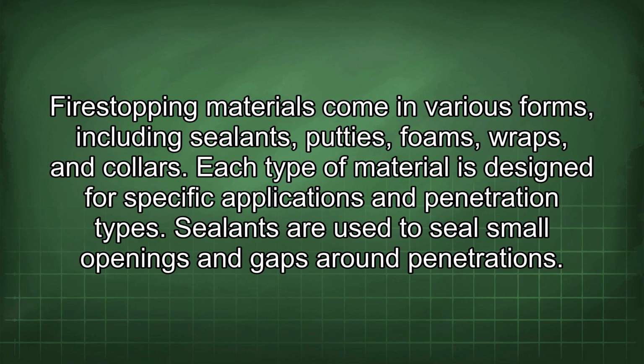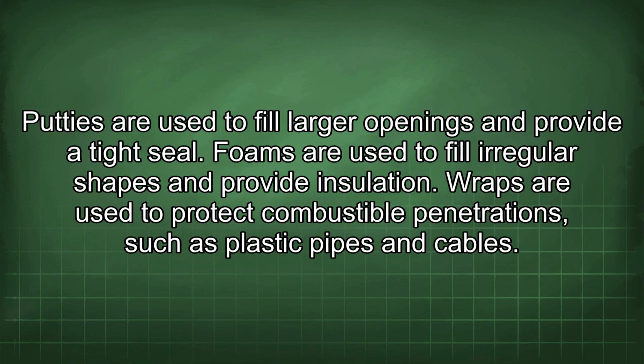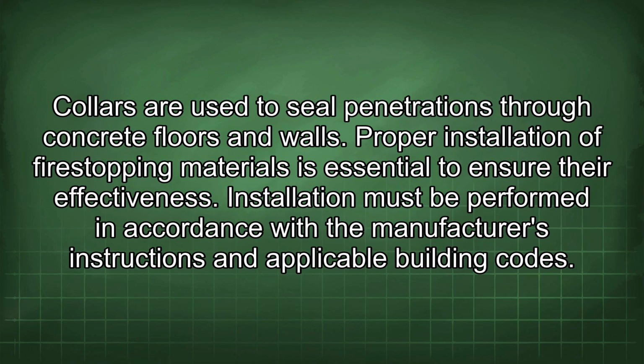Fire-stopping materials come in various forms, including sealants, putties, foams, wraps, and collars. Each type of material is designed for specific applications and penetration types. Sealants are used to seal small openings and gaps around penetrations. Putties are used to fill larger openings and provide a tight seal. Foams are used to fill irregular shapes and provide insulation. Wraps are used to protect combustible penetrations such as plastic pipes and cables. Collars are used to seal penetrations through concrete floors and walls.